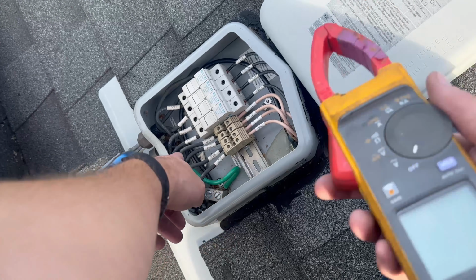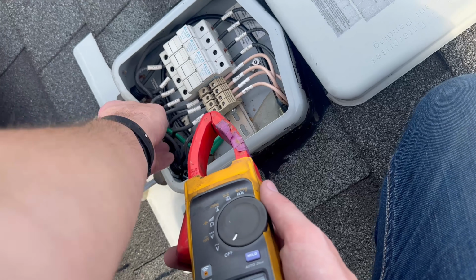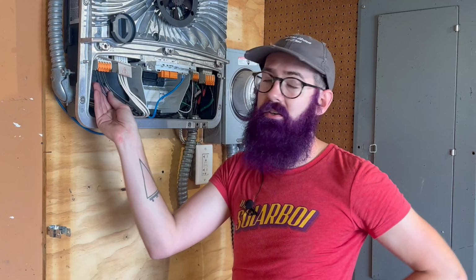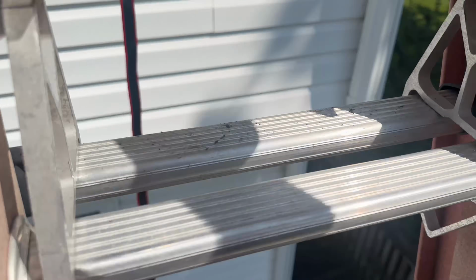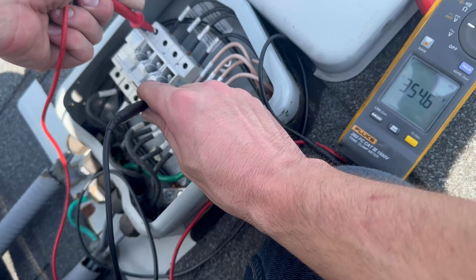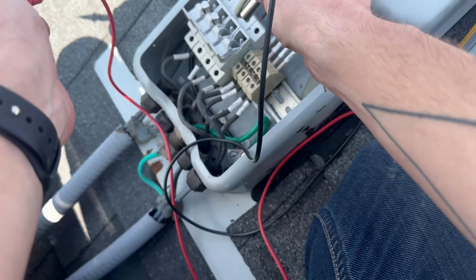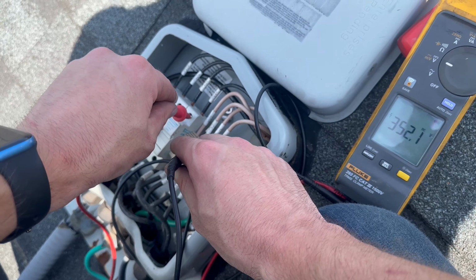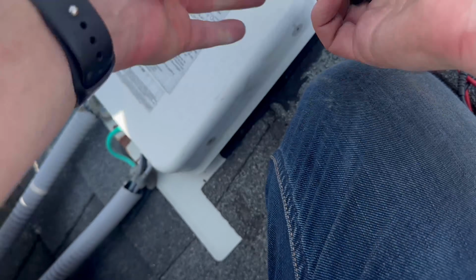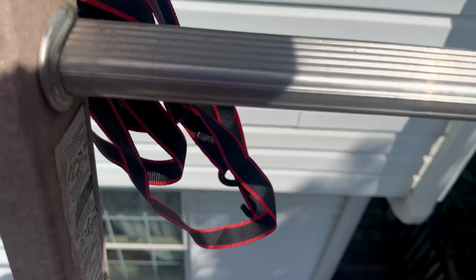And if you know the difference between ungrounded and grounded, you might also realize that I only have fuses on one set up there. When systems were grounded, you only needed to put fuses on the ungrounded wire. But now, because both sets of wires are ungrounded in the inverter, each set of wires needs to have fuses if you have over 3 strings on a maximum power point tracker. And here we are putting 2 in each, so we do not need fuses because only 2 strings are being bussed together at any given time. So short story is, we don't need to add fuses up on the roof, and I'm actually going to take away the fuses that are up there to increase reliability of the system with these bar fuses, because we don't need them. And if you don't need them, might as well increase the reliability of the system and not have those fuses accidentally blow when they aren't actually doing anything valuable.